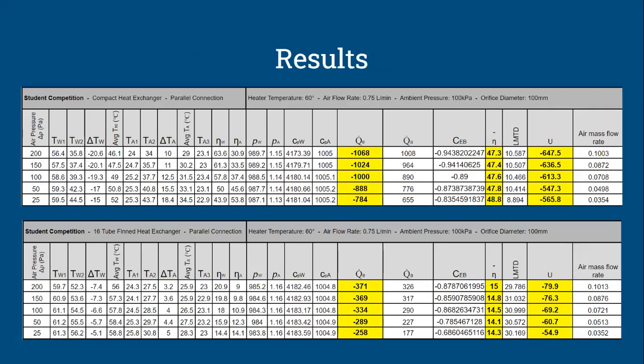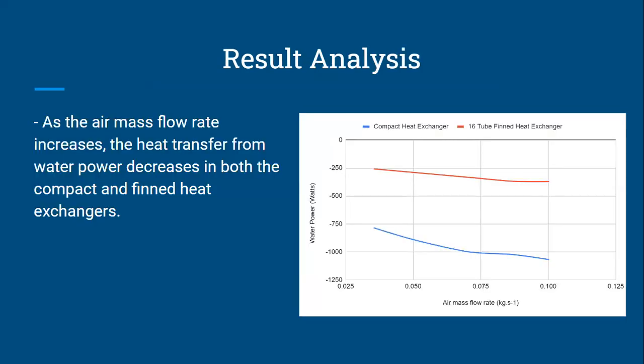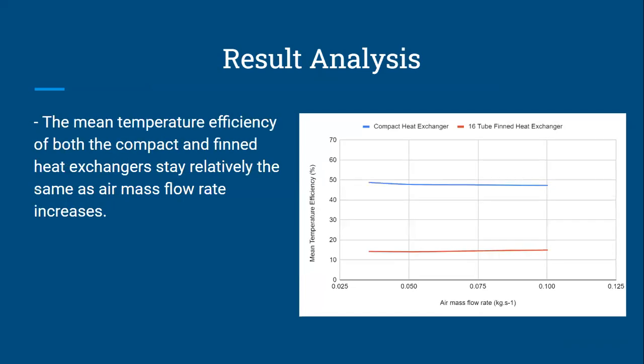So these are the results that we received from the two experiments, with the compact heat exchanger being on the top and the fin being on the bottom. In this graph, we can compare how much water power is being exchanged to the air mass flow rate. We can clearly see that the compact heat exchanger exchanges about 2/3 more than the finned heat exchanger, with both heat exchangers decreasing as the air mass flow rate increases.